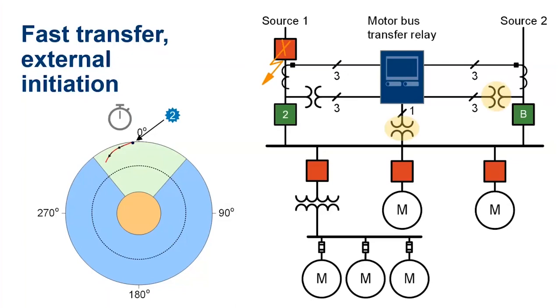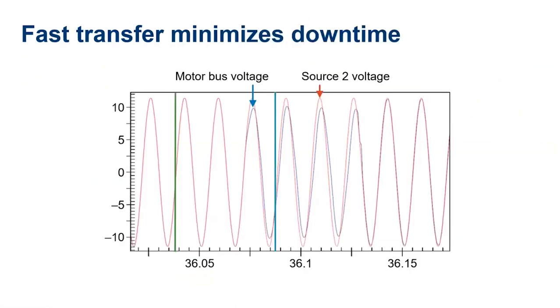Once we have confirmation that the breaker is open, we can send the signal to the other breaker to close. And since all that can be done quickly without having to do any heavy computations, we can have the breaker close in a few cycles, and then we get back to being at nominal voltage and at very close to the same phase that we had before.